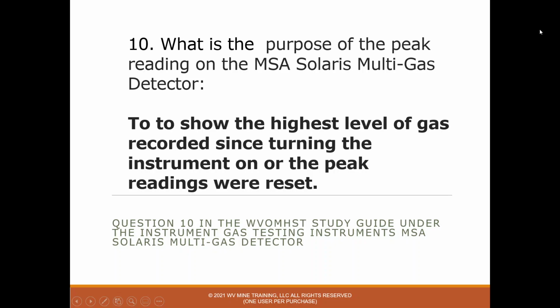But all these instruments have the ability to check the peak reading. So with the Solaris, you would push a couple buttons, and it would tell you the peak reading. And after you record that, you could push another button, and it would reset it back to its normal reading or normal range. So the peak reading is a very good tool on these, and you need to be aware of the instrument that you use, how to check the peak readings. And it does say you can reset it manually, or every time you turn it off and turn it back on, it will reset the peaks or the minimum to their original or normal readings.